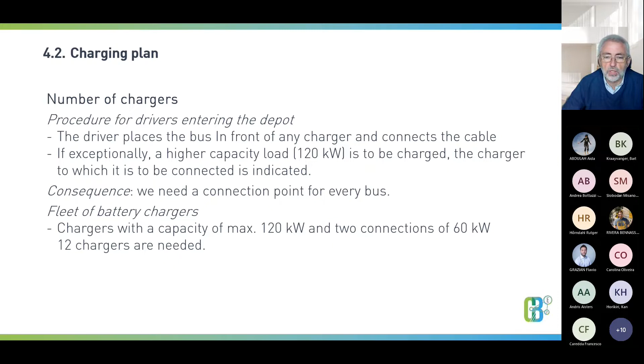Another option is to have a charger with 3 connections, 3 times 60, allowing charging at a maximum of 180 kilowatts. There you need 8 chargers instead of 12. Is this a saving? Not really, because if you have a charger with 2 connections, you can easily connect 2 buses with cables of the same length. If you need to charge 3 buses, you need a system with dispensers, where the dispenser hangs in front of each bus to be charged, for all 3 buses.